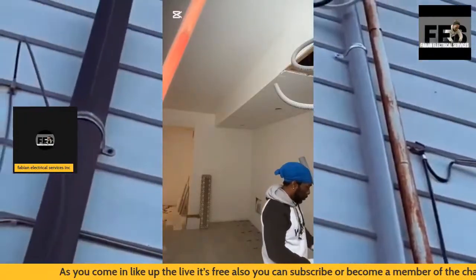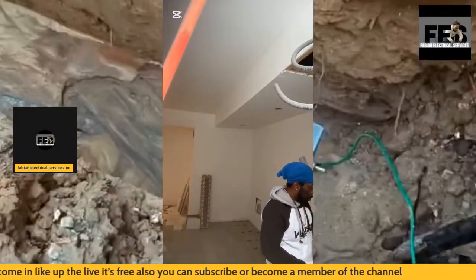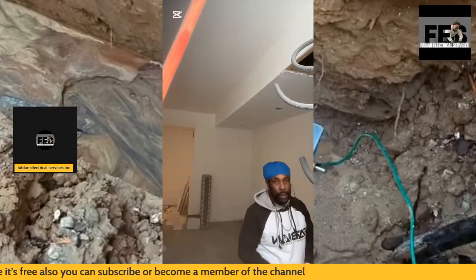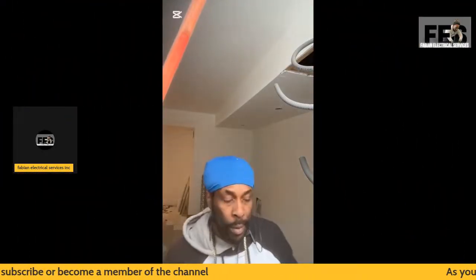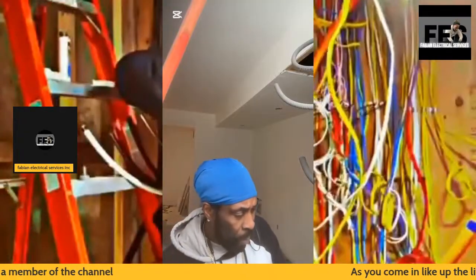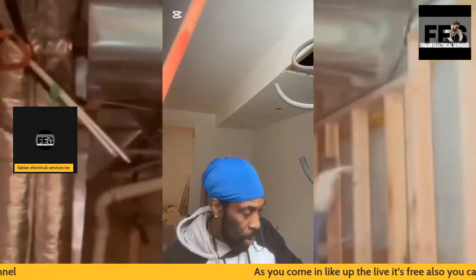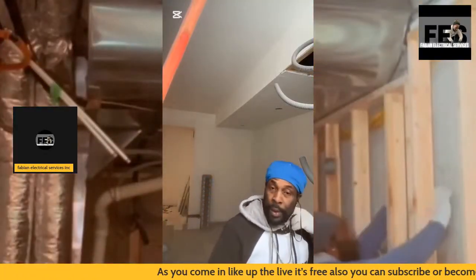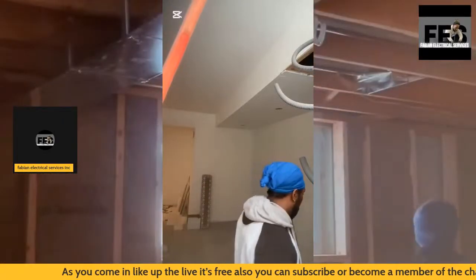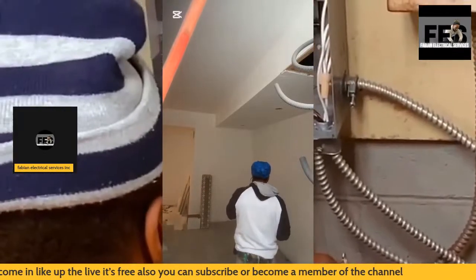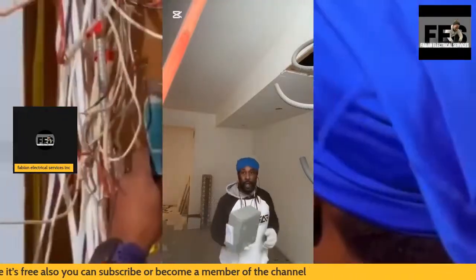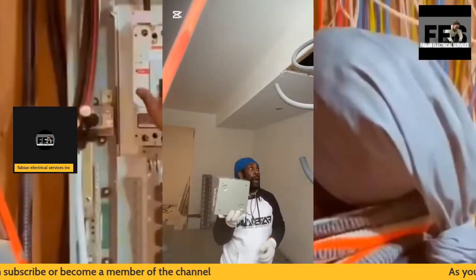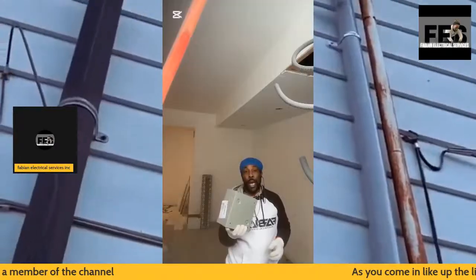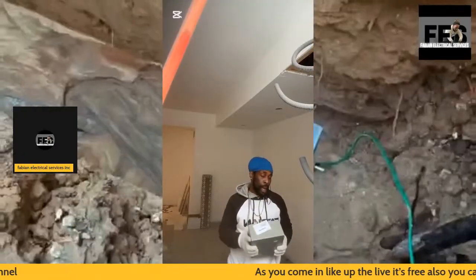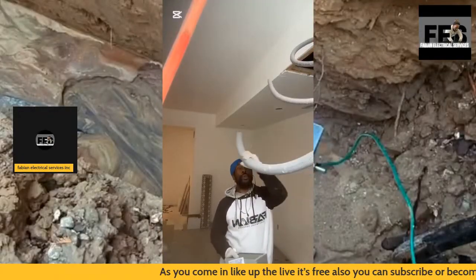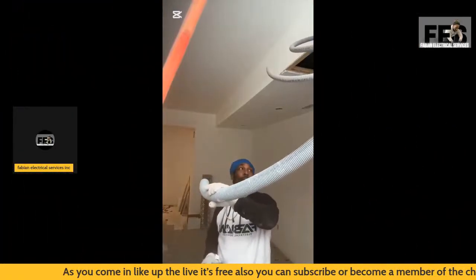It's very important to calculate what size wire you're going to use for the installation, what electrical boxes will be used, and what electrical conduit will be used, whether liquid type, PVC conduit, or NM wire. It's always best to figure out the type and size of wire and breaker size you're going to install before you start the electrical installation.